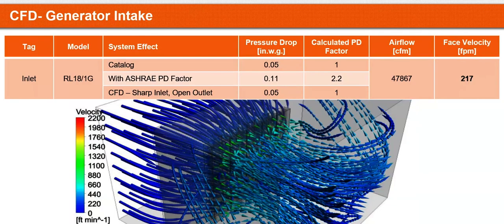This is another velocity vector profile showing you how the air comes in from the outside into the room. And although it speeds up very shortly after because of the size of the opening, it's going to slow down, keeping that pressure drop at 0.05 inches of water gauge. And that is important because if all of a sudden that was a quarter of an inch, imagine the people that might have to leave the building through that room, and all of a sudden you have negative pressure. So the radiator exhaust is ducted, so that's separate. That's not going to affect the room.